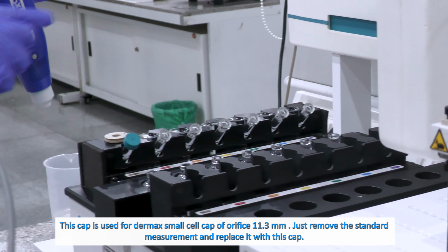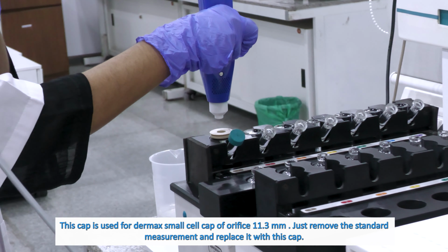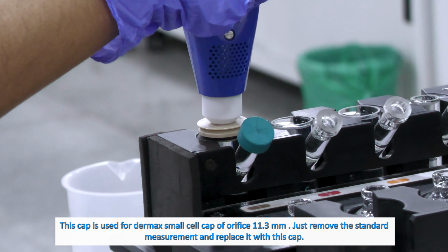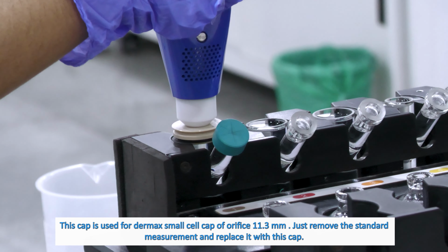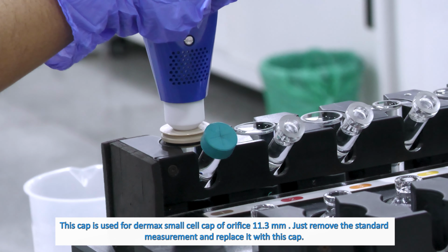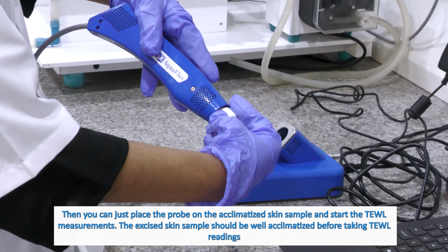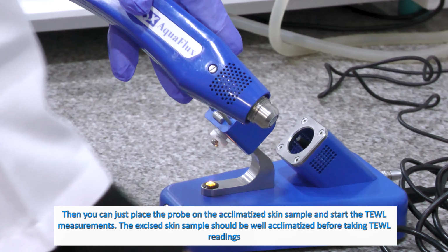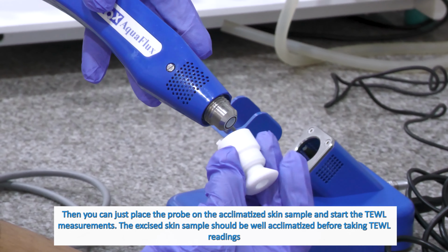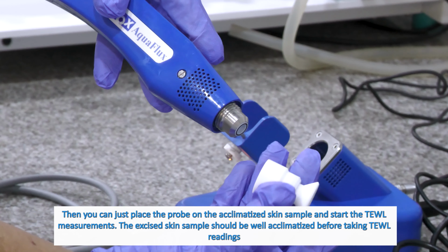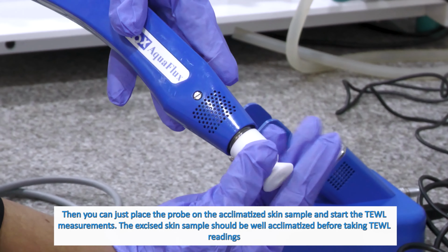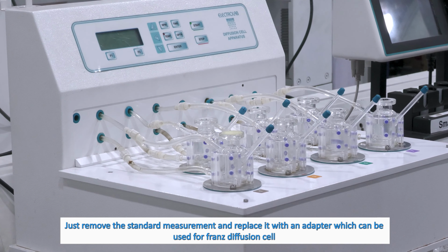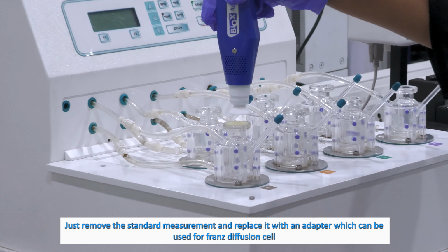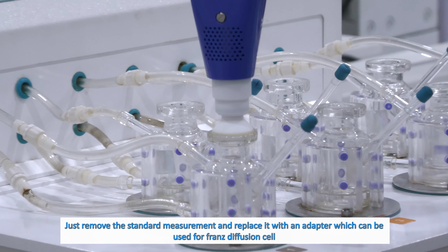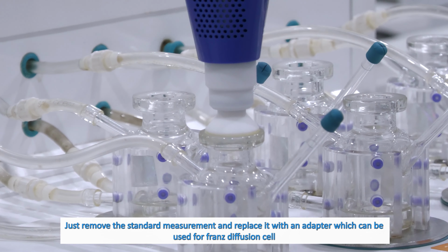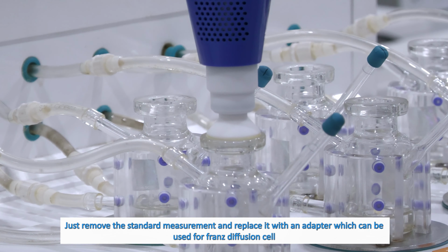This cap is used for the Dermax small cell cap of orifice 11.3 mm. Just remove the standard measurement cap and replace it with this cap. Then you can just place the probe on the acclimatized skin sample and start the TEWL measurements. The excised skin sample should be well acclimatized before taking TEWL readings. Follow the same procedure for the standard Franz diffusion cell. Just remove the standard measurement cap and replace it with an adapter that can be used for the Franz diffusion cell.